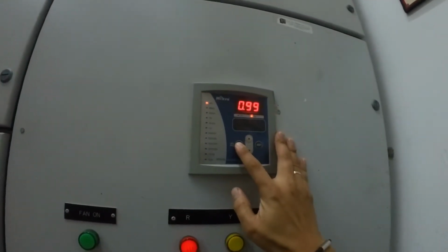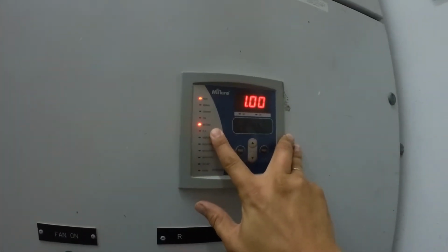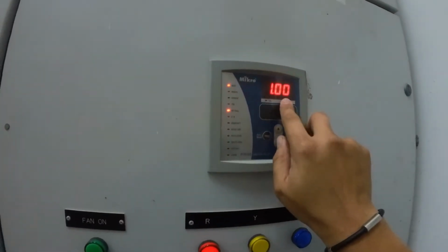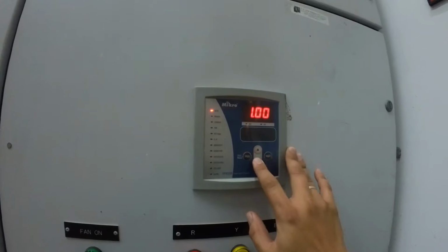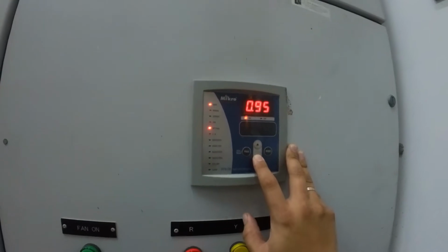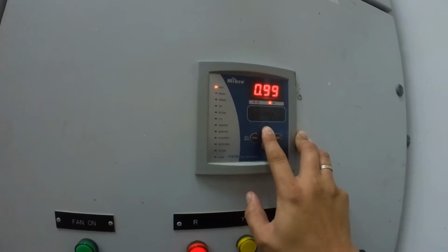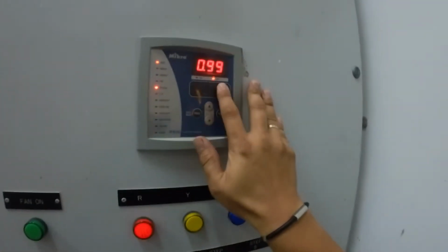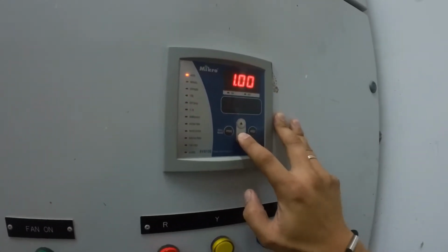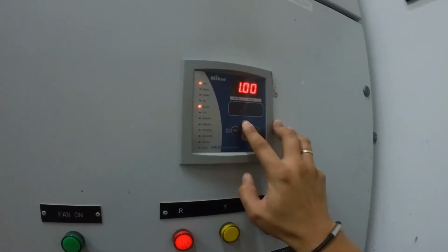To check the capacitor bank, first of all, we take a look at the set cos theta. That means the target power factor value. Here we have 1.00, which is unity power factor. You can program it to 0.98, 0.97 or 0.95. Best is to put it at 0.98. Or you can set it as overcompensate, which is on the capacitive side, but we don't recommend that. So it's best to set in the inductive area, 0.98. Here the installation is set at 1.